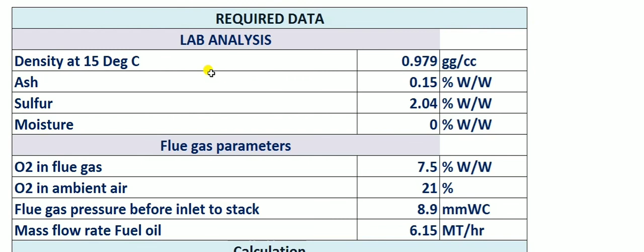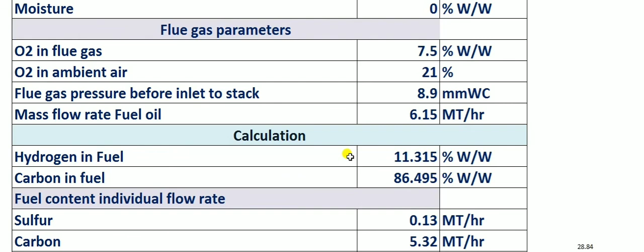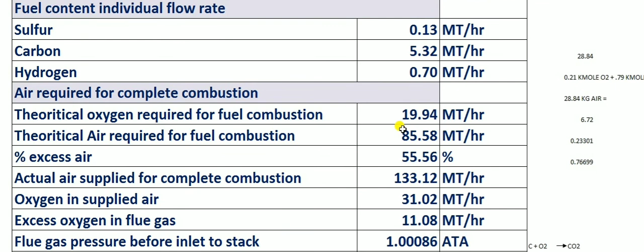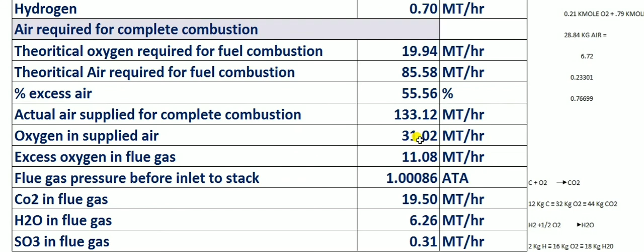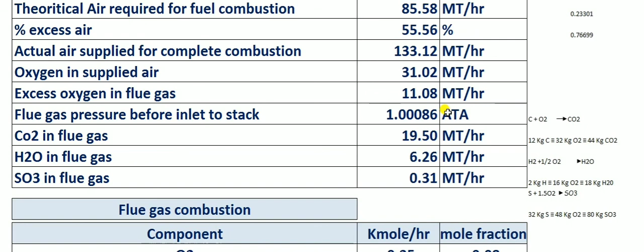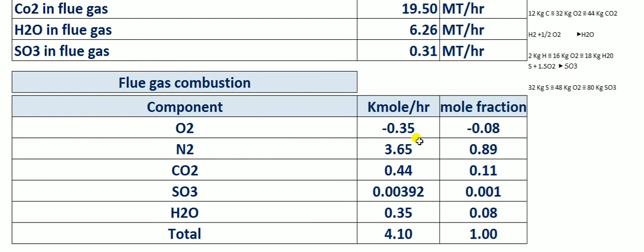So for this we need the fuel oil analysis, the flue gas analysis, and the pressure and mass flow rate of the fuel oil. By that we can calculate the hydrogen and carbon content. Into the flow rate we calculate the combustion air required for combustion, and how much oxygen is there. The flue gas pressure at the stack entrance we convert into atmospheric absolute. Then we calculate the mole fraction and apply this formula. In this you only need to enter two variables: the water mole fraction into total pressure, and the SO3 mole fraction into total pressure. That's it.